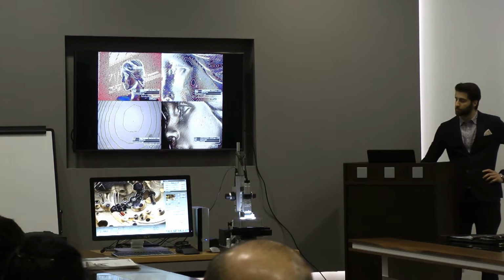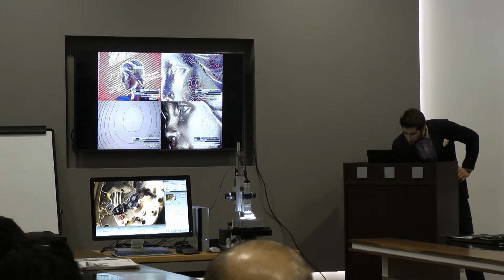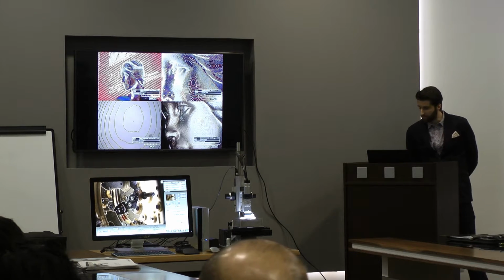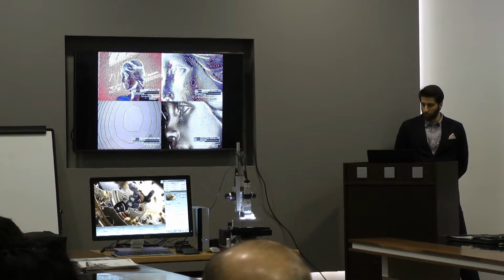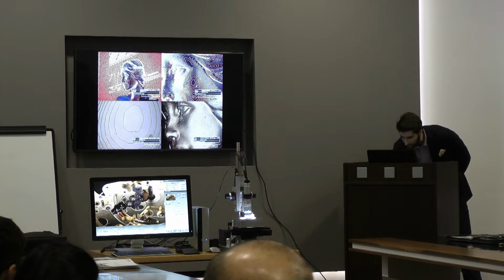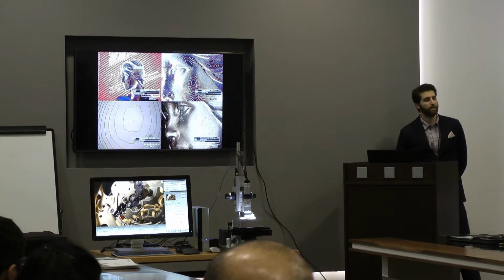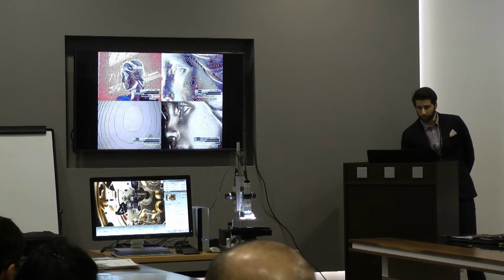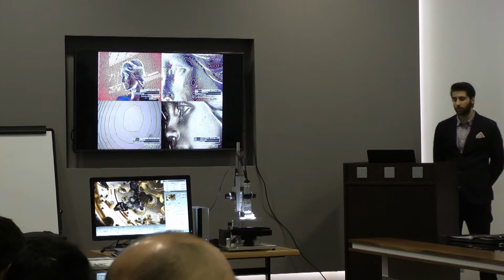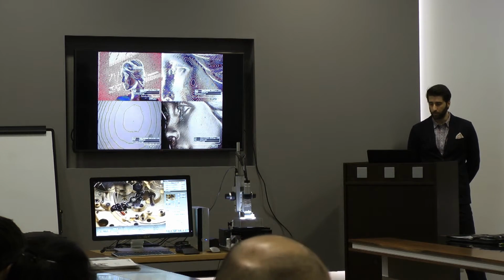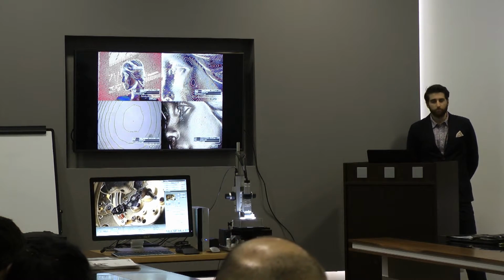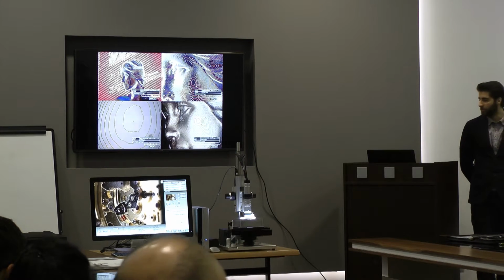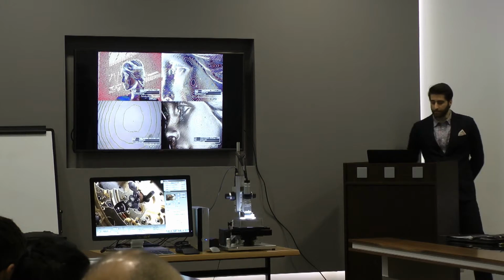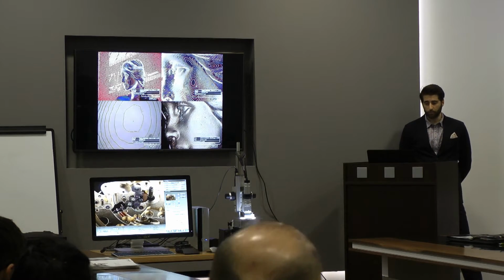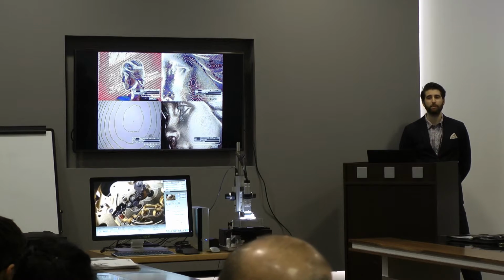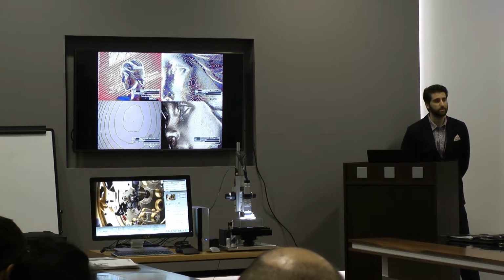So this is the revolver lens. A few pictures with the revolver lens. The first picture is from 35 magnification, the second is 140 magnification. The two pictures below are, again, 140 and 700 magnification, but with the other lighting system. It's also a Hirox patent we have. It's called ring light and coaxial light. You probably know those terms. Ring light is for use with low magnifications, coaxial light for use with high magnifications. In this case, coaxial lighting is much better to get the contrast better and to do measurements. Also for 3D measurements, the coaxial light with high magnification is much better.